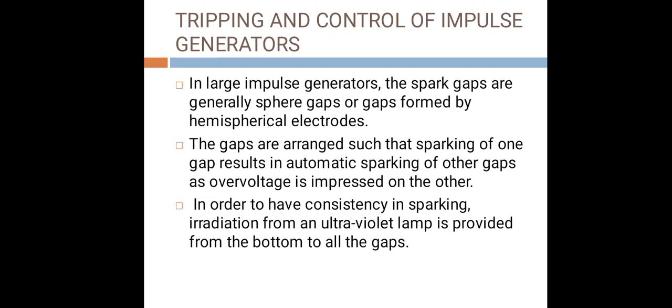In large impulse generators, the spark gaps are generally sphere gaps or gaps formed by hemispherical electrodes. The gaps are arranged such that sparking of one gap results in automatic sparking of other gaps as overvoltage is impressed on the other.